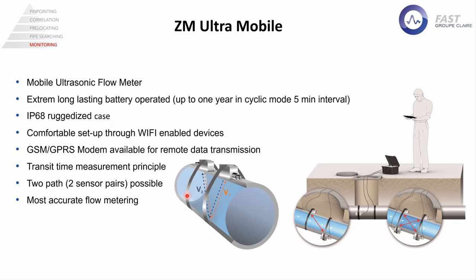With this device, which is also unique, you are able to measure two paths at the same time. That means it's for sections of the pipeline where you can't keep the five times D before the installation of the sensors and three times D after the installation of the sensors, if you have obstacles, reductions, bends, or whatever. Therefore, with this, you are able to connect two pairs of sensors at the same time.